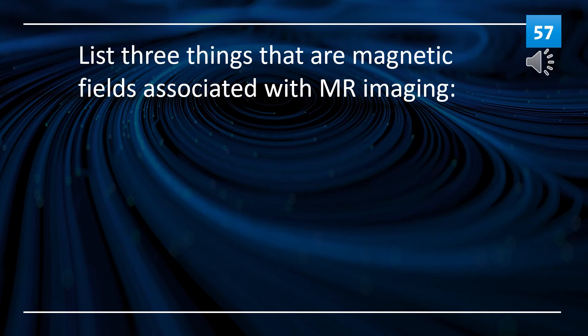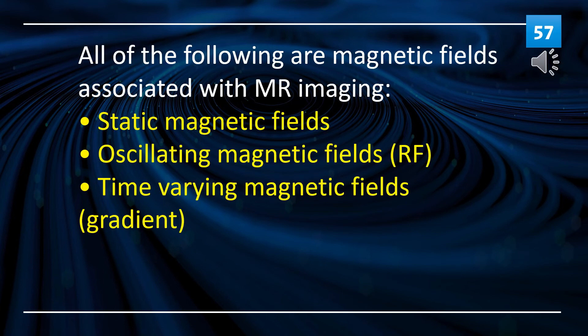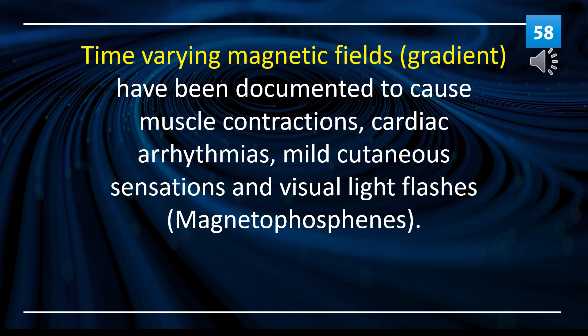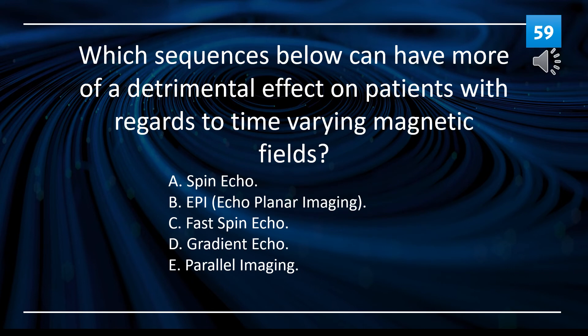List three magnetic fields associated with MR imaging: 1. Static magnetic fields. 2. Oscillating magnetic fields (RF). 3. Time-varying magnetic fields (gradient). Time-varying magnetic fields have been documented to cause muscle contractions, cardiac arrhythmias, mild cutaneous sensations, and visual light flashes (magnetophosphenes). Of the sequences — spin echo, EPI, fast spin echo, gradient echo, and parallel imaging — EPI (echo planar imaging) can have more of a detrimental effect on patients with regards to time-varying magnetic fields.